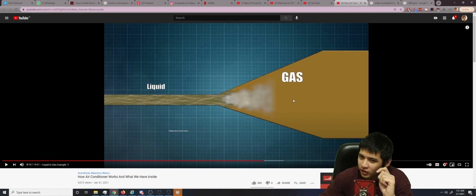Okay, here's the thing. The liquid doesn't turn into gas inside the filter dryer. It does that inside the evaporator. That's why there's a thing called superheat, and it's a measurement done on the suction line and the pressure of the refrigerant.